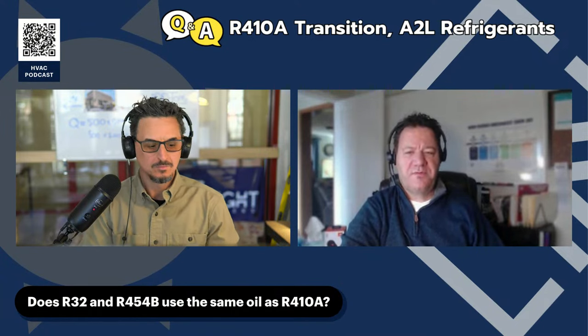Yeah, and if you want to reference that, this goes back to my Copeland days - you can go to any compressor manufacturer's AE bulletins, application engineer bulletins. Copeland's would be the application engineer bulletin 93-11. If you go to 93-11 for Copeland, that will show you all the refrigerants, all the oils, and what applications they're allowed into. You'll see that POE oil or whatever oil they're using, whether it's PAG, mineral, or whatever - you'll see what that application is. It's spelled right out there with all three that you have on the screen now.